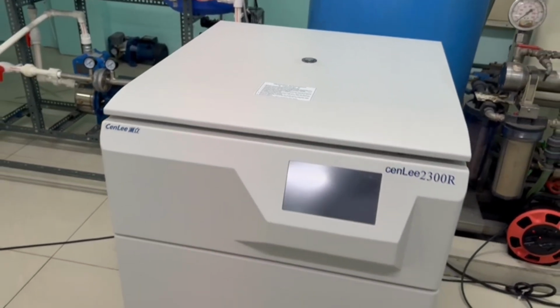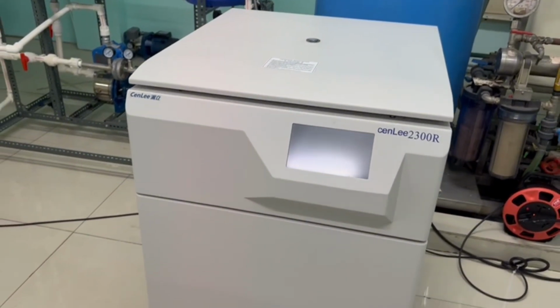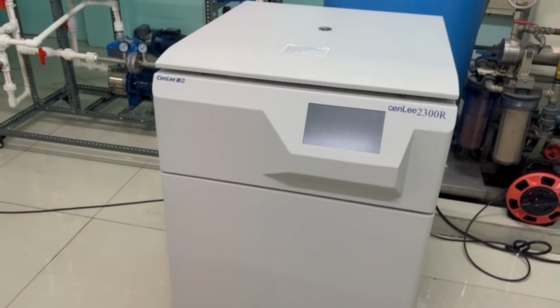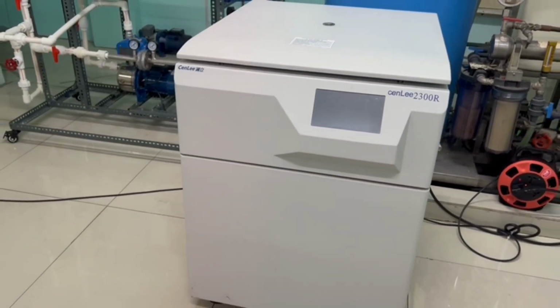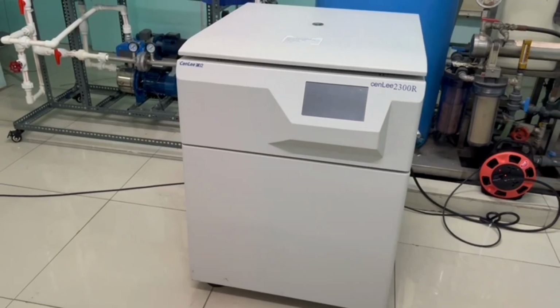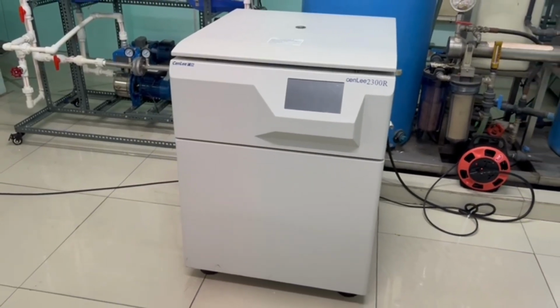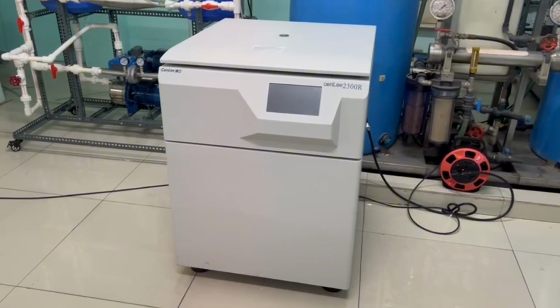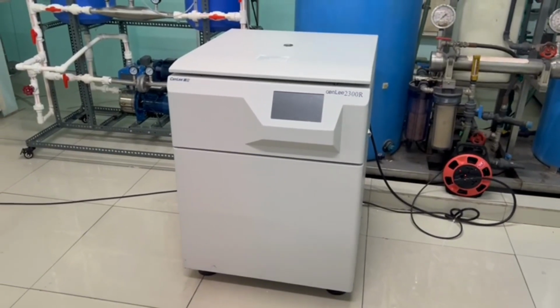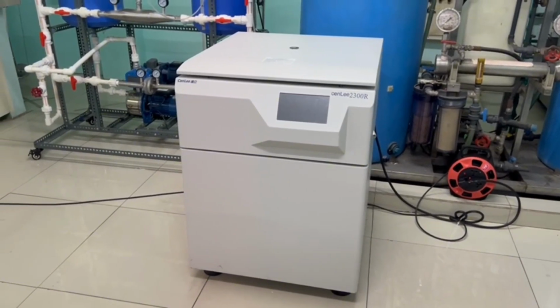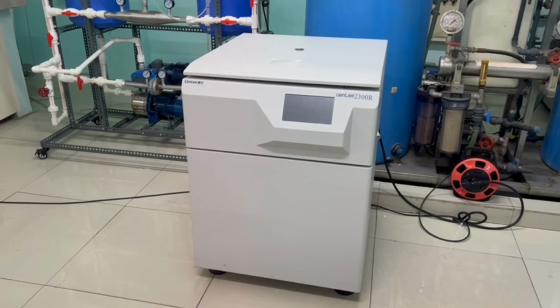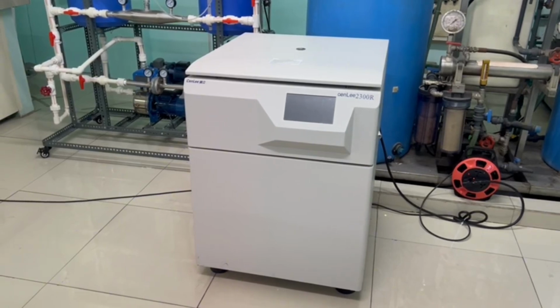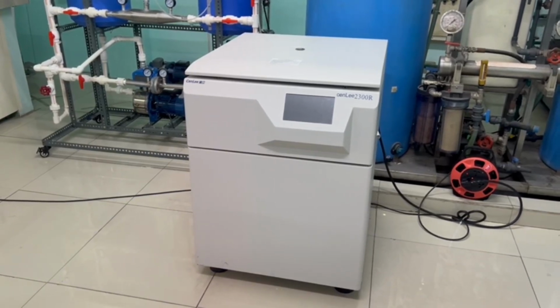Warnings. Check the rotor before using for running. Any cracks, even small ones, cause risks of the rotor breaking during high-speed revolution. Do not use a rotor with cracks. Do not use a rotor with corrosion defects. Do not use a rotor that exceeds its life cycle. When maintaining the instrument, disconnect the supply at least 3 minutes before disassembling the front cover. Otherwise, there is a risk of electric shock.